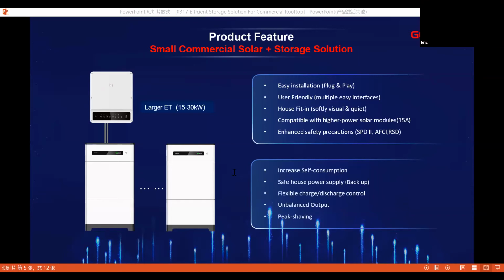From GoodWe side, the GoodWe inverter output can be adjusted for power factor. So for example, the GoodWe inverter can output reactive power to increase your power factor. So this is our solution, and for most commercial rooftops, we can solve the power factor issues.